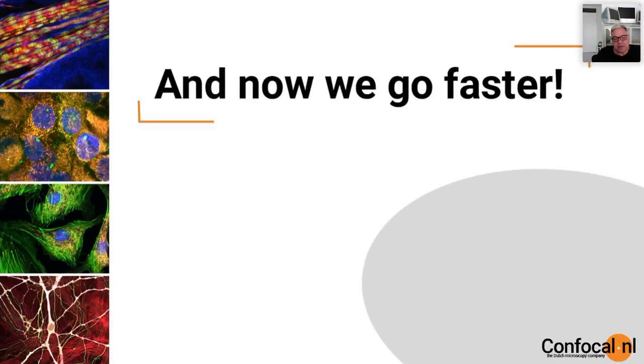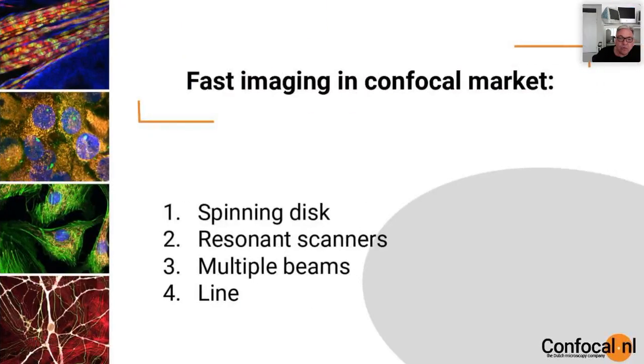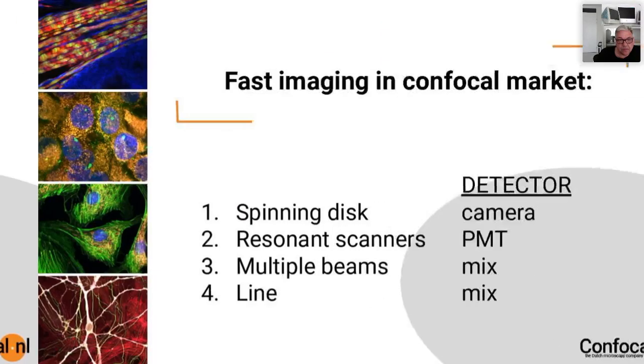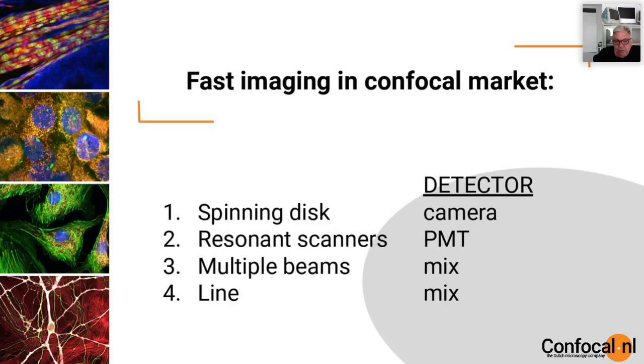I want to start by going back to the history of fast imaging confocal microscopes — they're not new, they've been around for a while. You have different flavors: spinning disk systems, resonance scanners, multiple beam systems, and line scanners. The detector matters a lot: in fluorescence you want minimum light exposure and low phototoxicity, so you want the most sensitive detectors. Cameras are the most sensitive — more sensitive than photomultiplier tubes used by resonance scanners. Spinning disk systems use cameras; multiple beam systems have a mixture.